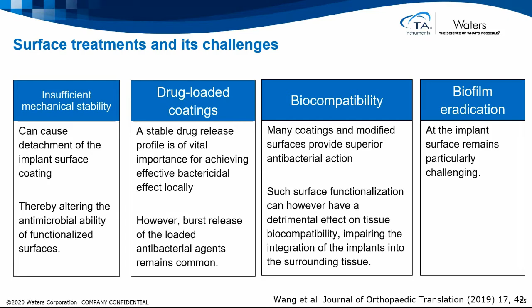Biocompatibility can be measured by IMC by the principle that mammalian cells do produce heat as well. Everything that lives will produce heat. The metabolic heat of a cell is about 30 picowatt per cell, which means in microcalorimetry we have the possibility to measure the metabolic rate of between 10 to 50,000 cells. Microcalorimetry can then continuously measure this rate and see how it changes upon exposure to a material. So we can use microcalorimetry to measure the cellular response to synthetic biomaterials in vitro.